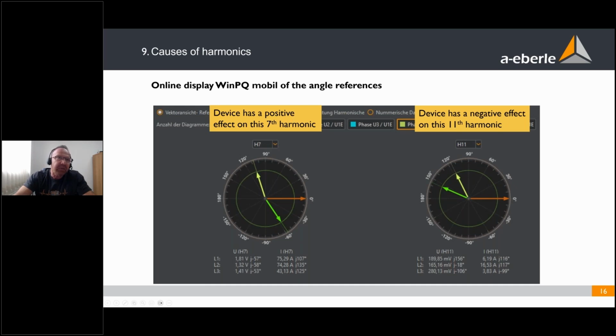The other effect we have on the 7th harmonic, the disturbance of the grid is here, and this device with about 75 amps of the 7th harmonic is producing in this angle position. You can imagine that if this device is running, or a big plant is running, it's a positive effect on the 7th harmonic at this point. So if you're interested in more information about supraharmonics or the phase angle we calculate for harmonics, please have a look at our webpage. You'll find many technical articles and many video clips to explain our features and also these technical problems.